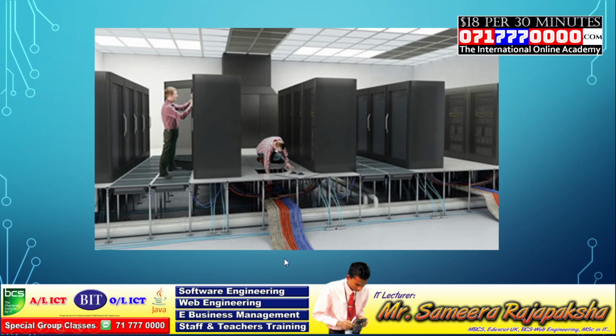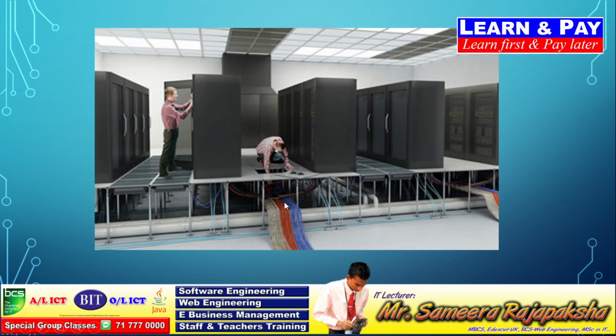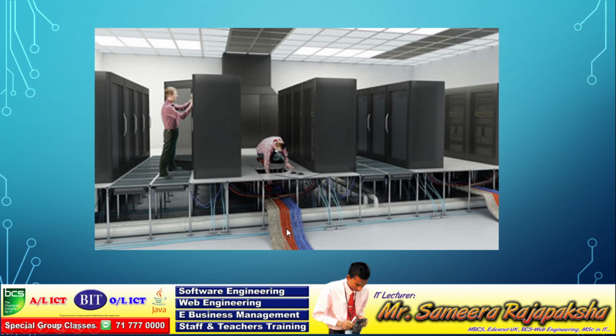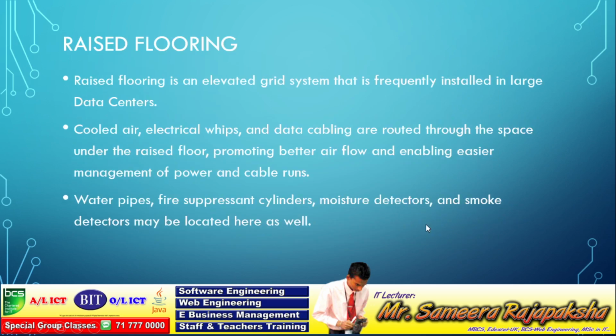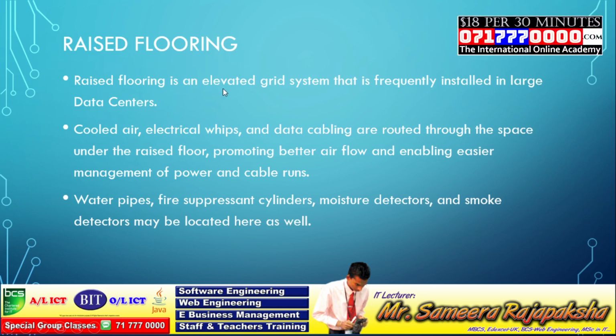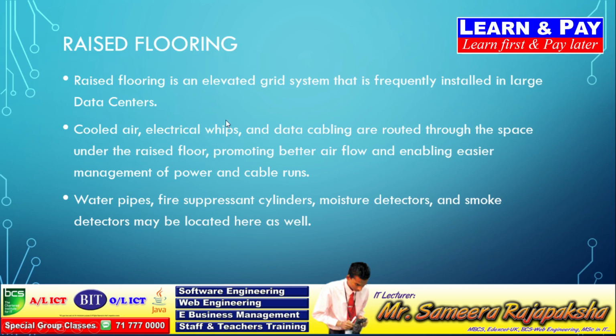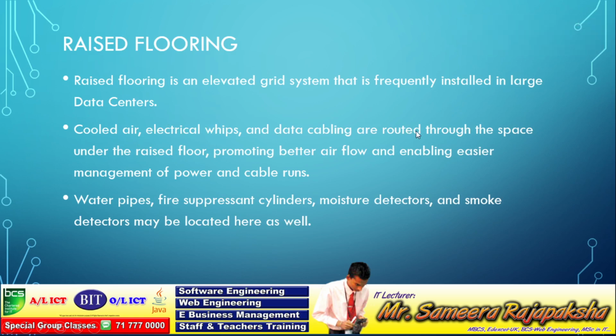Under the raised floor, we can see these types of components and other data center based equipment, cabling, cooling pipelines, and electricity supply. I mentioned it in the previous slide: raised flooring is an elevated grid system that is frequently installed in large data centers. Cooled air, electrical whips, and data cabling are routed through the space under the raised floor, promoting better airflow and enabling easier management of power and cable runs.